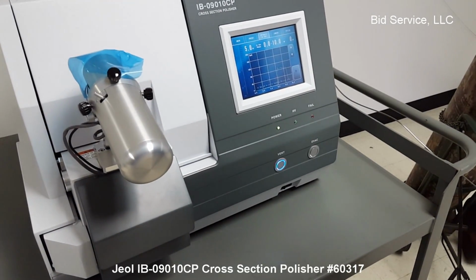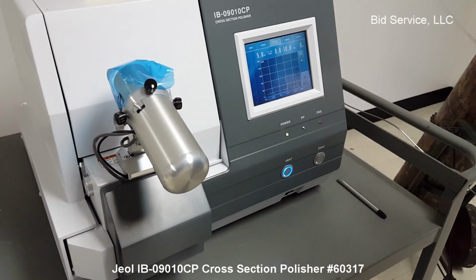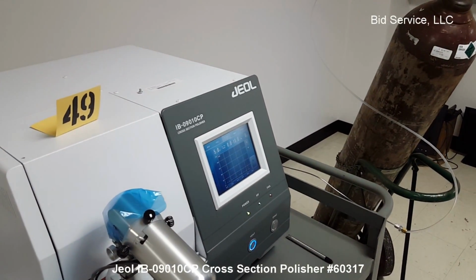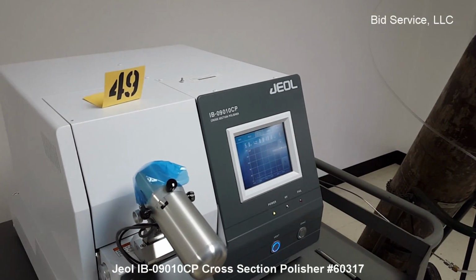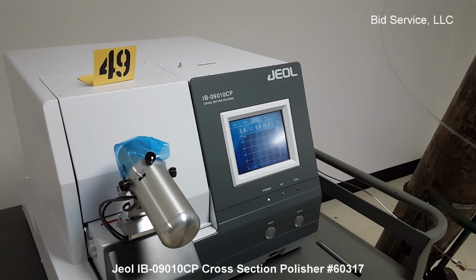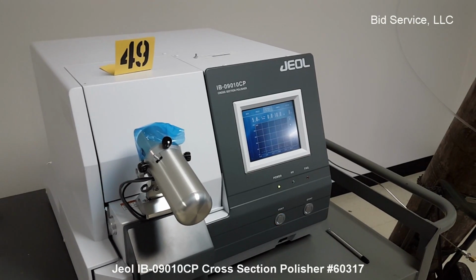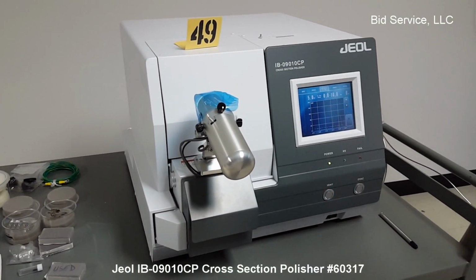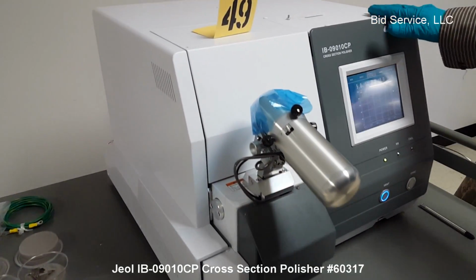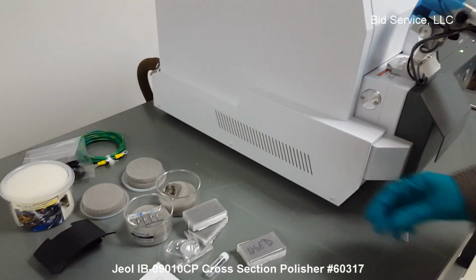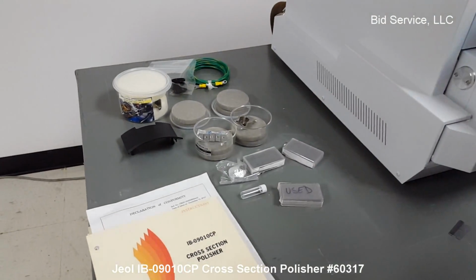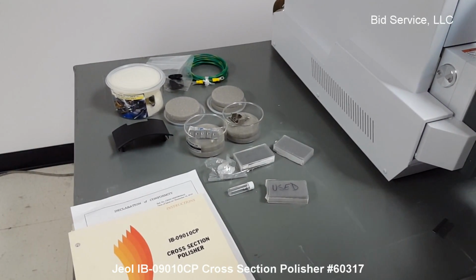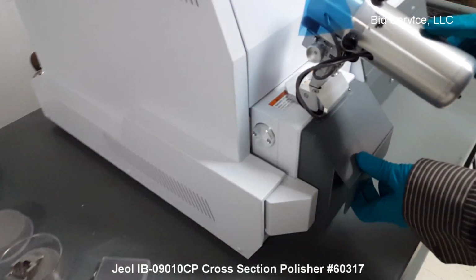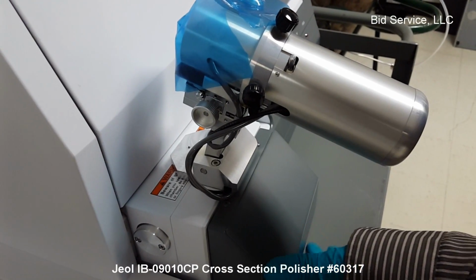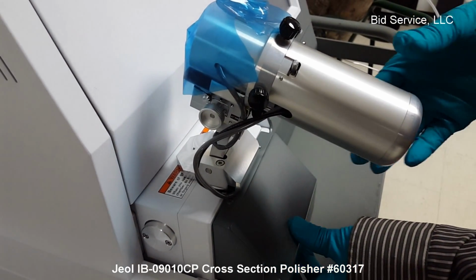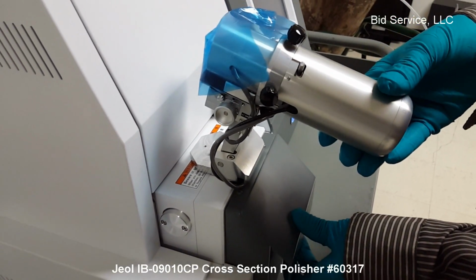So I'm going to vent the chamber. Right now, argon gas is connected from a bottle to the system. The set pressure should be about 28 psi, or about 2 bar. Additional accessories will be included with the system. There are used shields and extra sample holders. The system will be shipped with the microscope detached from the unit so that the camera is not damaged.